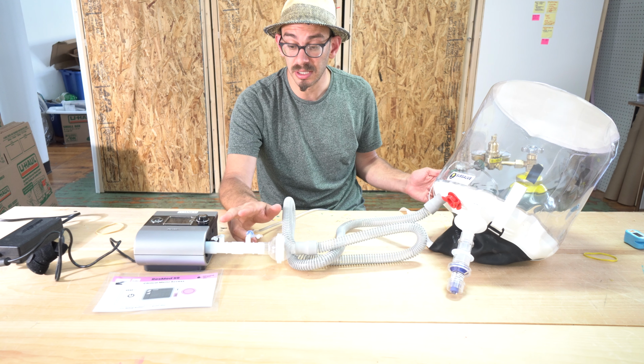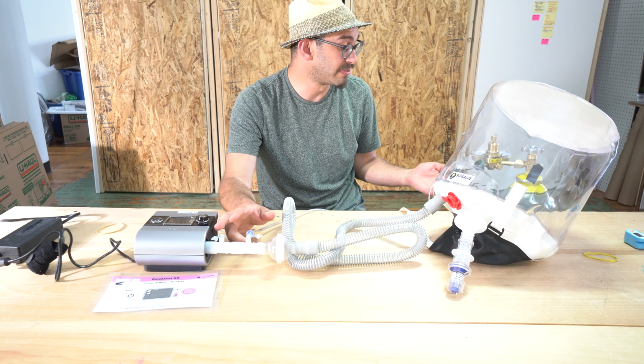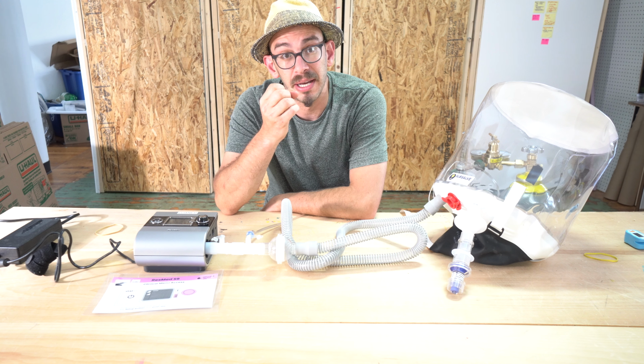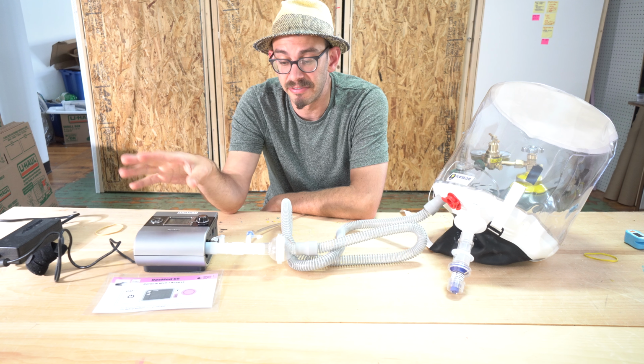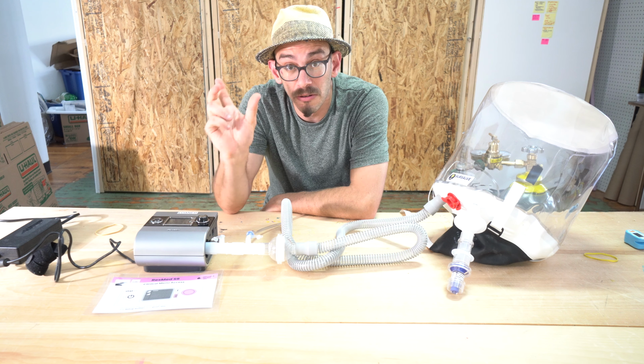Now, this oxygen enrichment adapter, this is very counterintuitive. It's not extra. It's actually important that you leave it open. And you'll see that this is going to allow air to flow out. The reason for that is that these machines are designed for home use, and they are designed to try to detect if the tube is blocked. And if so, they will turn off. The way they detect that is they see if there is a very low flow going from the machine into the circuit, because they can sense flow within the machine.